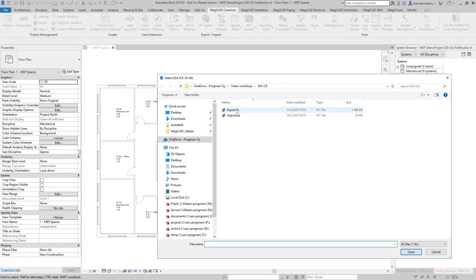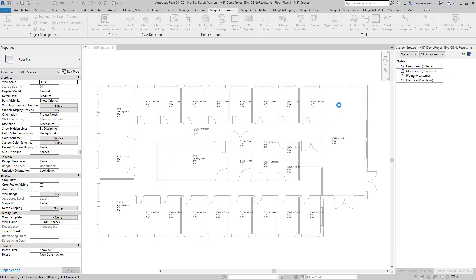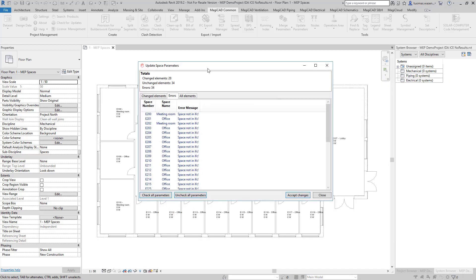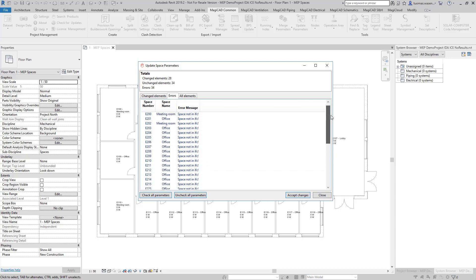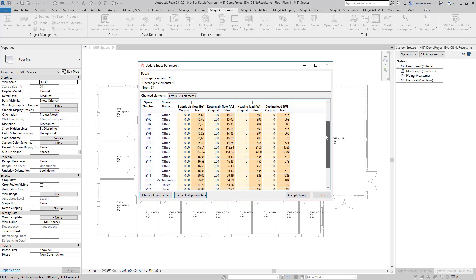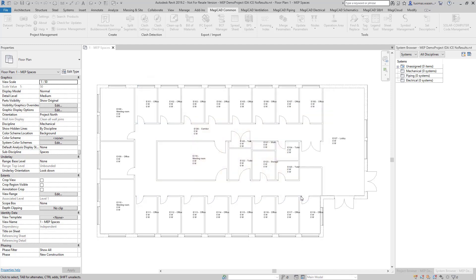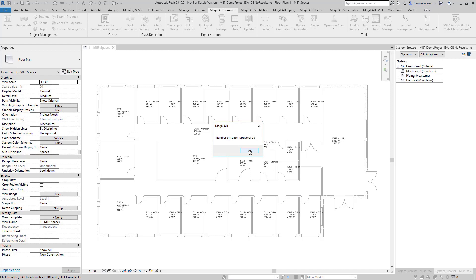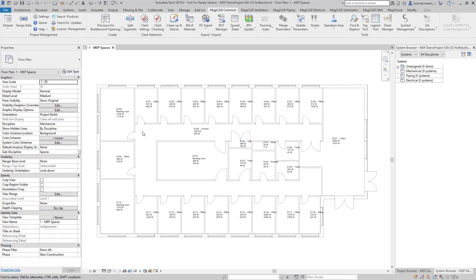We have import.ifc. What we see here first of all are the errors that we have: space numbers, space names. Just by looking at the numbers I'm checking that those are second and third floor spaces. Of course I don't have any information on them because I didn't run any calculations or simulations on them in this case. But from the Changed Elements tab I can see the spaces with their numbers and names and the changed values. Check all parameters, accept changes, then the information is updated to these spaces.